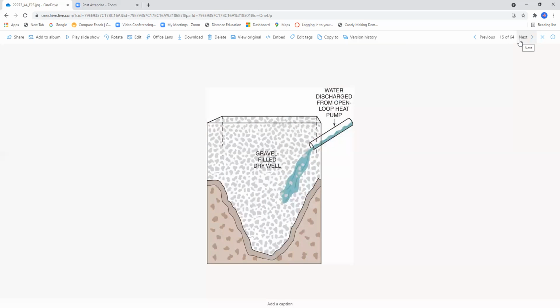Okay, here we have a situation. They show an area that is filled with gravel. This is found on page 44.23. This is a dry well. So what's happening is this well was utilized at some time previously, and now it's filled with gravel. And basically we are rejecting discharge water from an open loop heat pump system into this dry well. The theory behind this is we can recharge the aquifer because the water is going to collect around the gravel, and that in turn is going to hopefully allow minerals to either be picked up or be released into the rock formation. And of course, this water will find its way down to the water table.